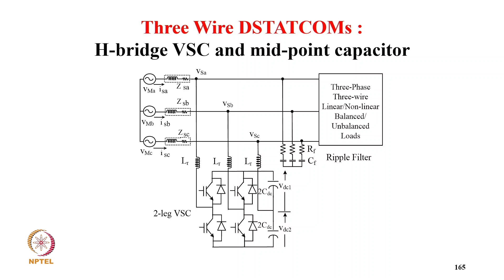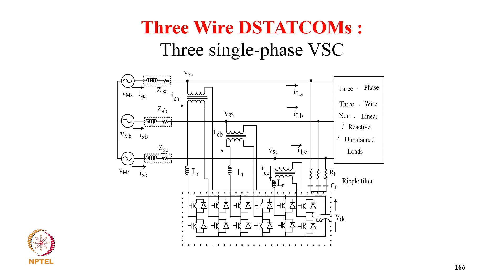This topology is considered quite important because you keep the power electronics cost low at low voltage, and it works like a shunt compensator. That really allows proper voltage matching. And in the single phase H-bridge, there is an advantage that your ripple voltage frequency can be just double the switching frequency with proper control. That reduces the inductor requirement as far as ripple current is concerned. And apart from that, the ripple filter at the point of common coupling avoids the switching noise. Of course, here the switching noise is less because you are typically using a transformer in between.